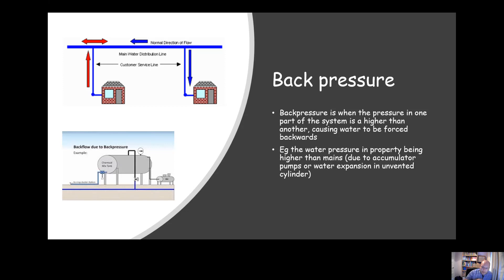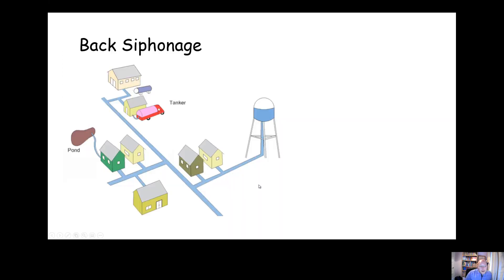A good example of back pressure would be an unvented hot water cylinder being fed from the mains. If it doesn't have a check valve on it, when that water heats up and expands it can cause water to be forced backwards in the pipework. So we should make sure we put a check valve on the cold supply to an unvented cylinder.